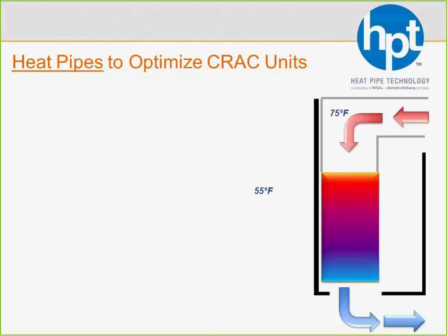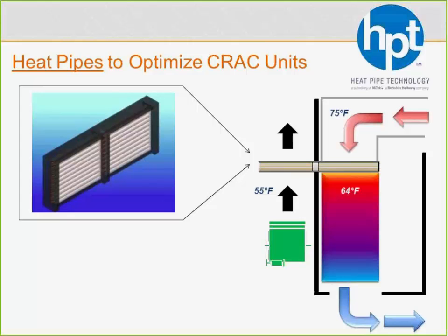So let's say the data room is set for 75 degrees. I believe that's what ASHRAE recommends. So anytime that it's cooler than 75 degrees outside, we could essentially use the heat pipe as a heat sink to whisk that heat away to the cooler outside air environment to cool that air before it goes back into the CRAC unit.